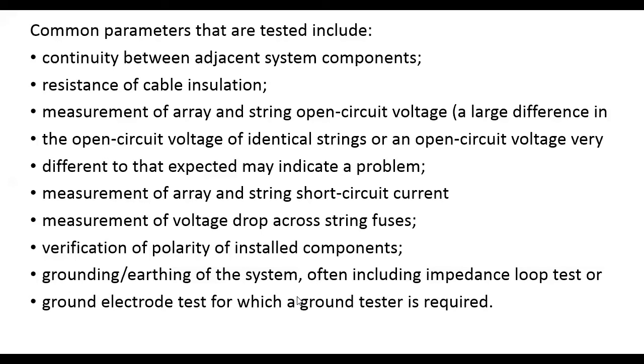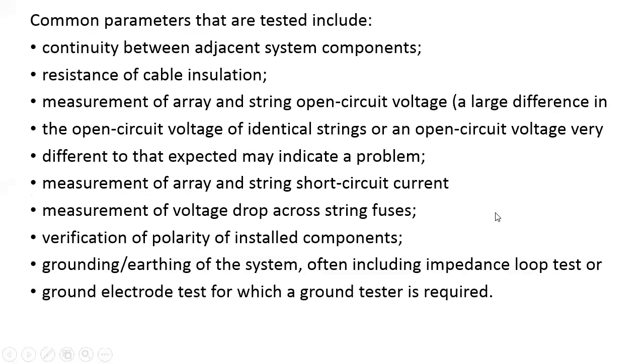Then the ground or the earthing of the system, often including an impedance loop test, or what we call a ground electrode test, for which a ground tester is required. Using a ground tester, we have to check whether proper earthing or grounding of the system has been ensured and done properly. So there are many things we have to do before we hand over the complete PV system to the customer. So the testing has to be done properly by the right person.